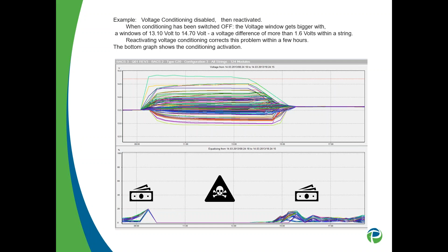This is a neat slide. When you're looking at voltage balancing or conditioning, you're saving money and extending life when those batteries are balanced. Otherwise you get into zones where you have the potential of overcharging, undercharging, and lower capacity. When they're getting overcharged, you also have the potential for thermal runaway.